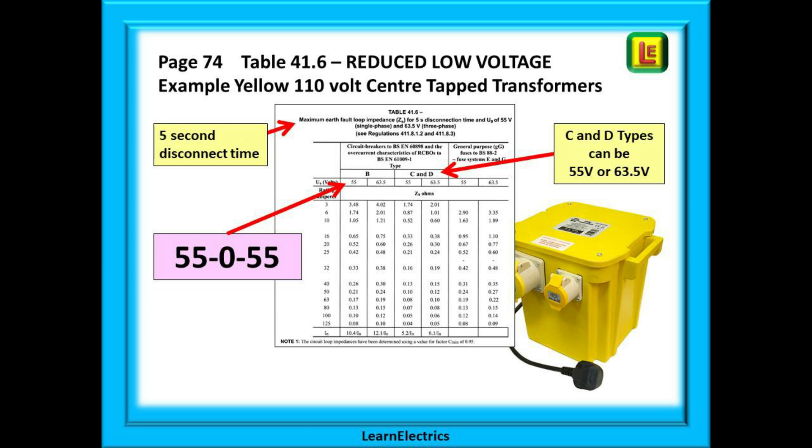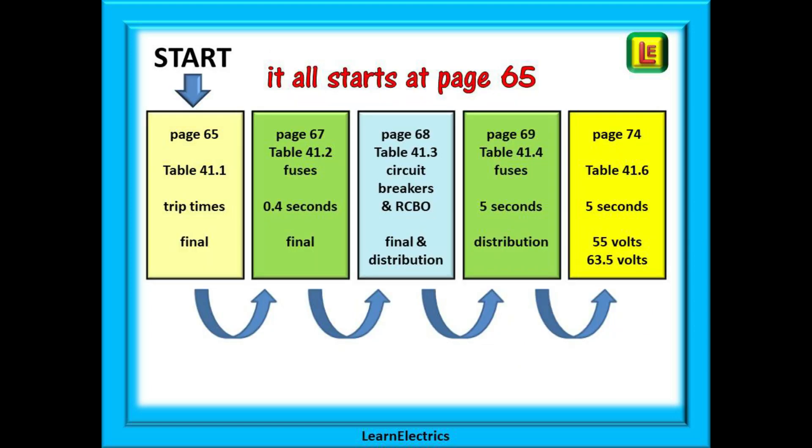Only a 5 second disconnection time applies to these circuits. And they cater for types B, C and D circuit breakers. Also, do not be confused by the C and D column. Types C can be 55 volts or 63.5 volts. And so can type D. We will do a couple of examples shortly.